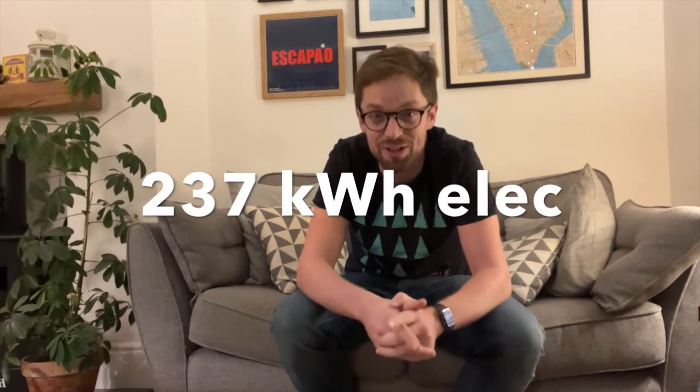So how is it performing — energy, cost, emissions, everything? Our heat pump has been running for more or less five or six months now. Until the start of October, it was mainly just providing hot water for showers, washing up, and hand washing. Over the last few weeks and months, we've started to rely on some heating. Interestingly, those two things — heating and hot water — mean the heat pump operates at different efficiencies. When our heat pump was installed, we also had a heat meter and electricity meter installed on the connections so we can keep a record of how much heat and electricity it uses, and from that work out the efficiency, or coefficient of performance. I started keeping a record in the third week of October, and by that point, for the first four months of operation, it had delivered 700 kilowatt hours of heat using 237 kilowatt hours of electricity, with an efficiency or coefficient of performance of just under three.